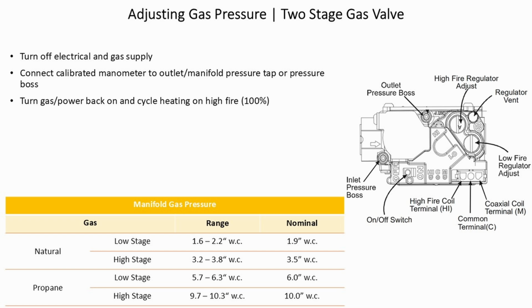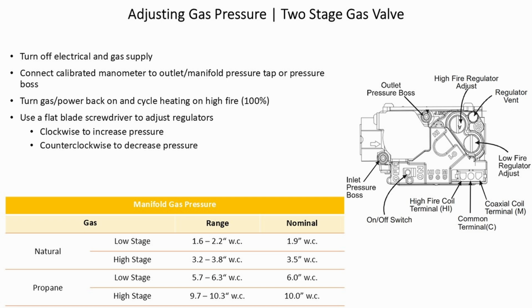Turn the gas and power back on and cycle heating on high fire, 100%. Use a flat blade screwdriver to adjust the regulators. Turn the regulator screw clockwise to increase pressure, counterclockwise to decrease pressure. Single-stage furnaces will use the same gas pressure as the high-fire stage on a 2-stage furnace.